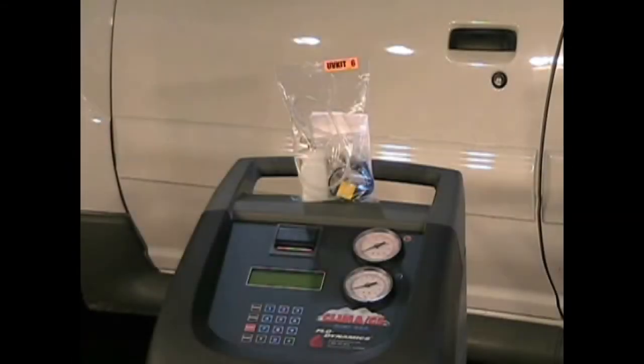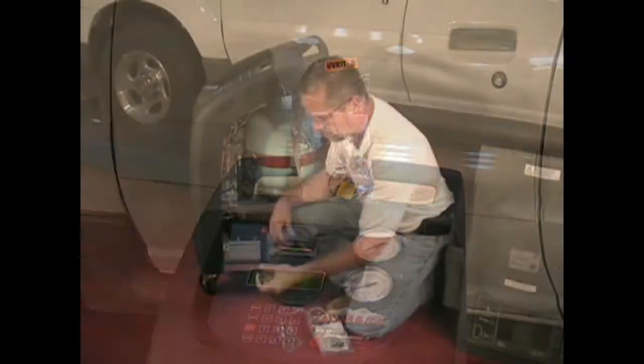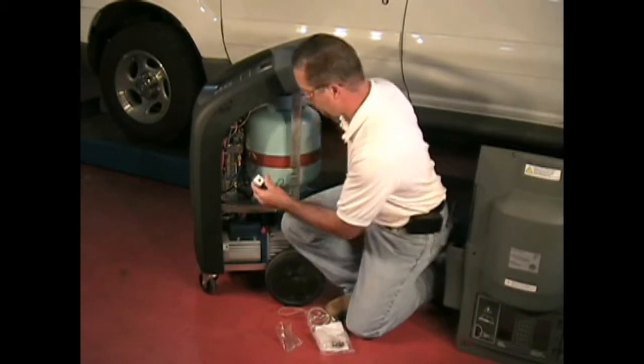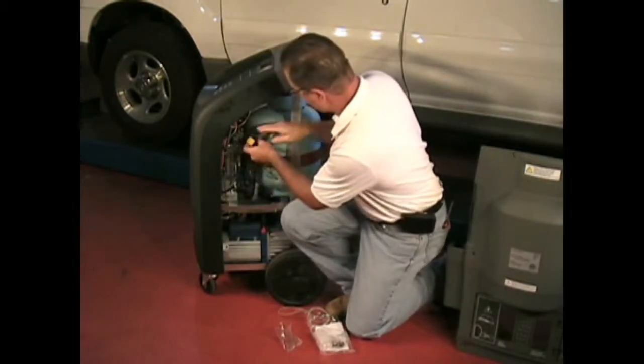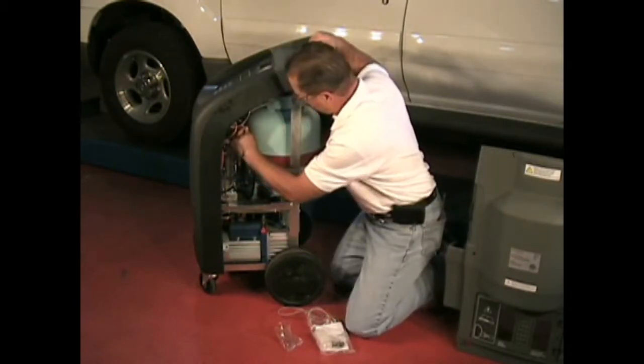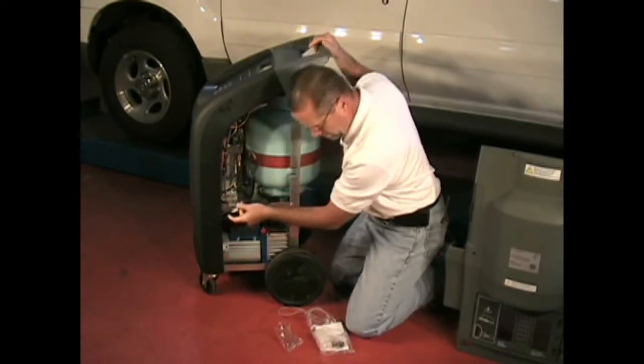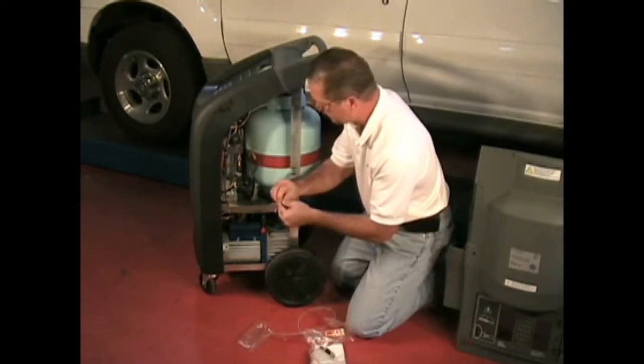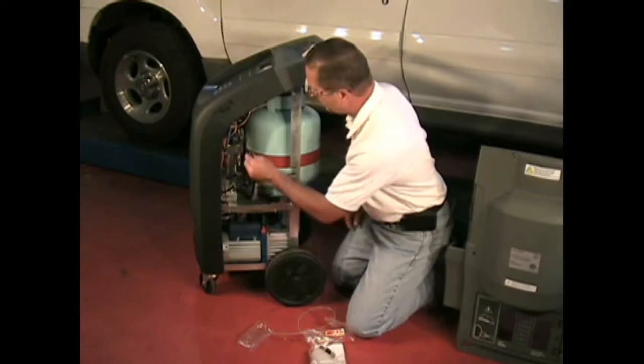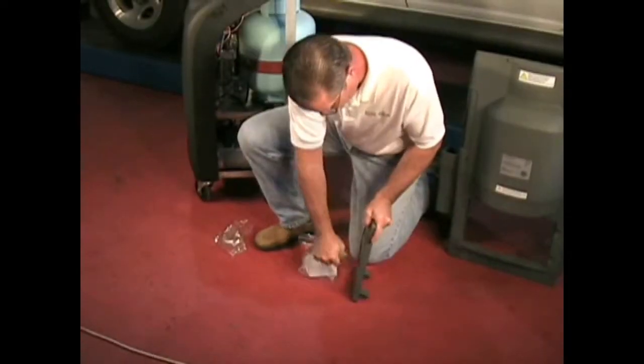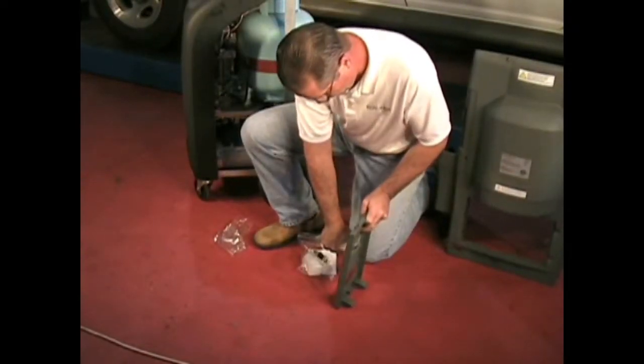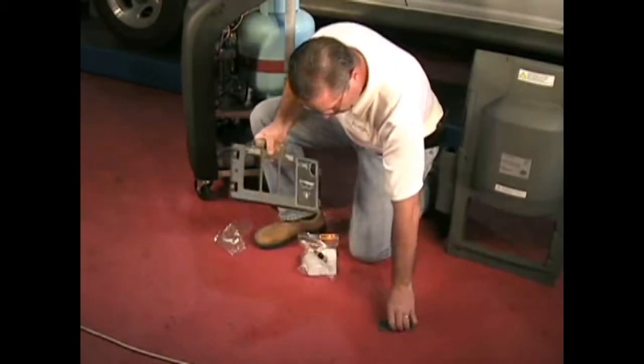The DK300 dye injection kit enables you to install oil and dye along with refrigerant charge, and do so in an automatic, completely hands-off sequence. To install the DK300, place the solenoid coil on the provided plunger post located on the back top side of the manifold. Use the locking washer and nut to hold it in place. Next, cut out the center access panel on the lower back removable panel.